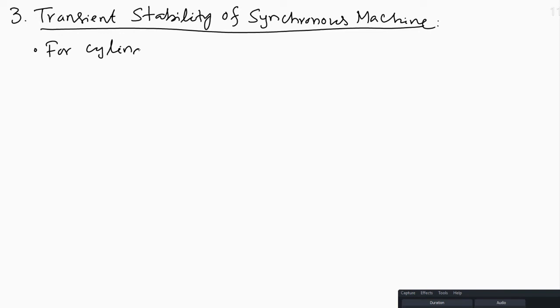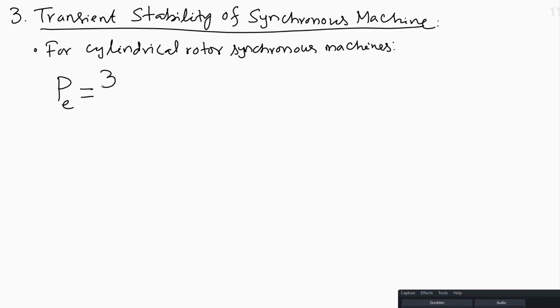So, for cylindrical rotor synchronous machines, the developed power Pe is given by, for a 3-phase machine, 3 Vt into Ef divided by Xs whole into sin delta, where Vt is the terminal voltage, Ef is the no load induced EMF, Xs is the synchronous reactance, and delta is the load angle or torque angle or power angle.